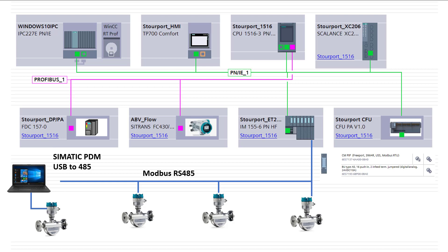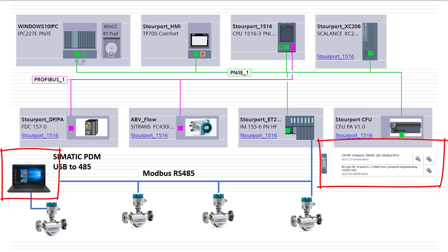The downside to Modbus 485—and this is probably the main issue that you'll have—is we can't have two Modbus Masters talking to the slave at the same time. So this card here, this CM module, is a Modbus Master.